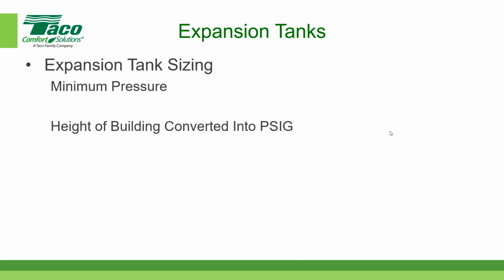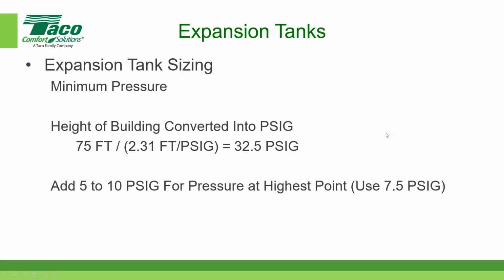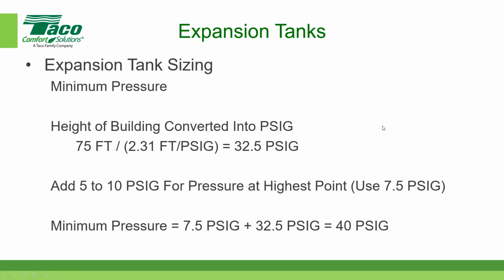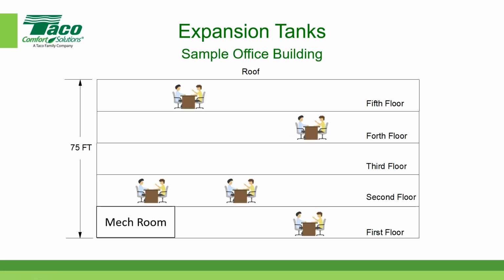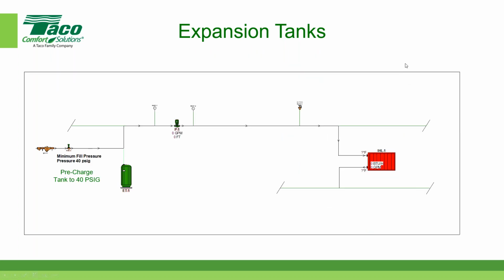Well, we had the height of the building converted into PSIG. That means the height divided by 2.31 was equal to 32.5 PSIG. We added somewhere between 5 to 10 pounds, and I like to use 7.5. So if we added 7.5 to the top, we get 40 pounds at the bottom. So that's the minimum pressure. So in our simple building, our minimum pressure at the expansion tank is 40 PSIG. That's also the fill pressure controlled by the pressure regulating valve.